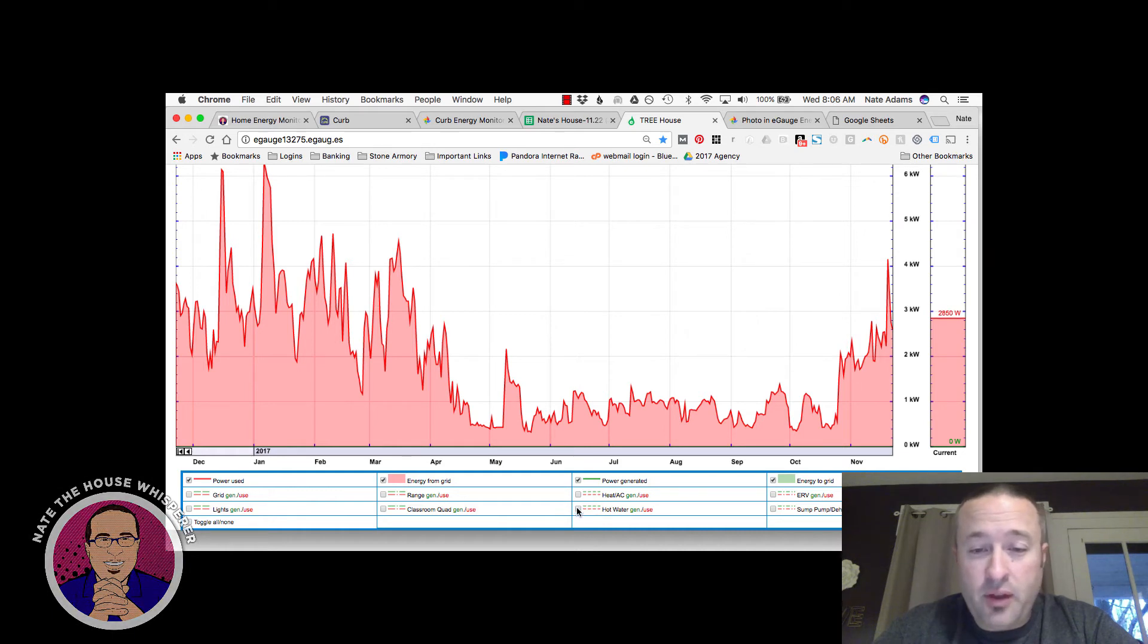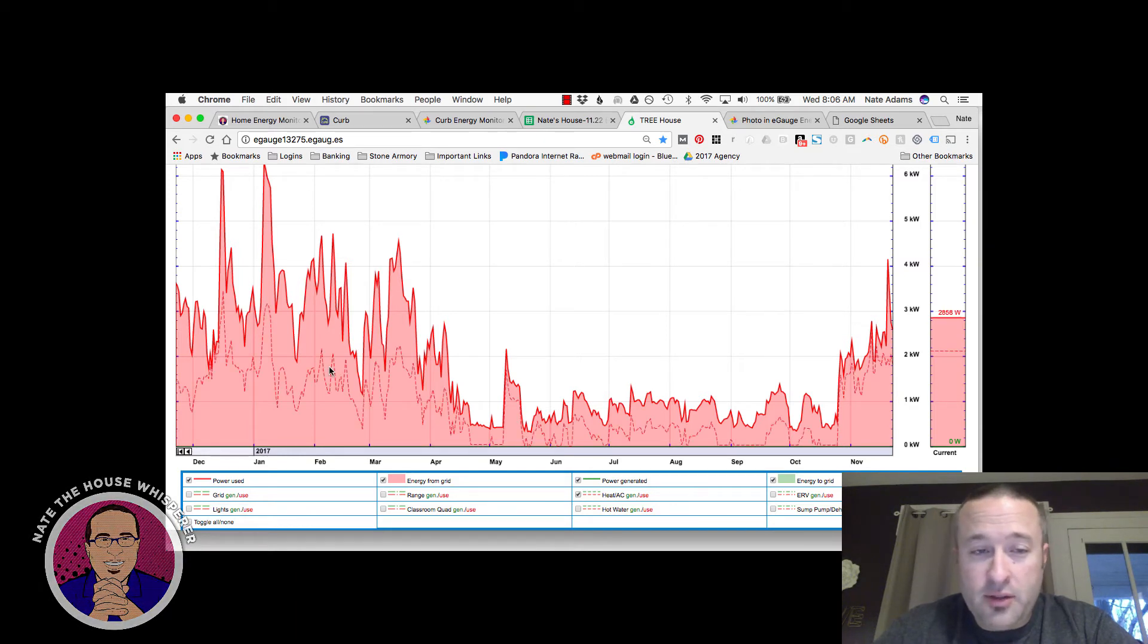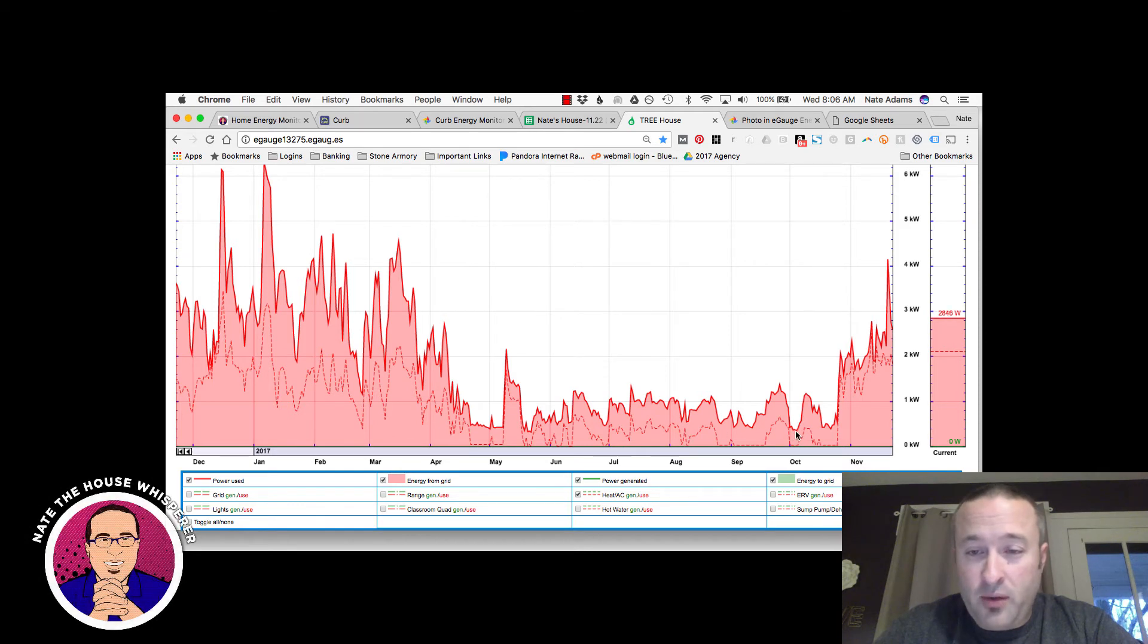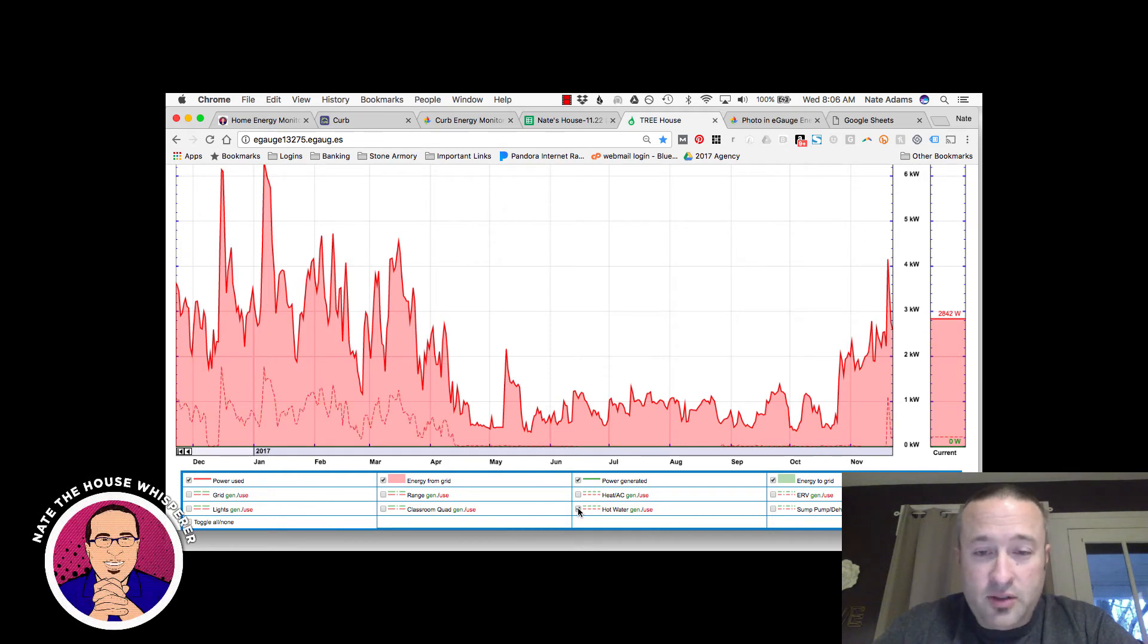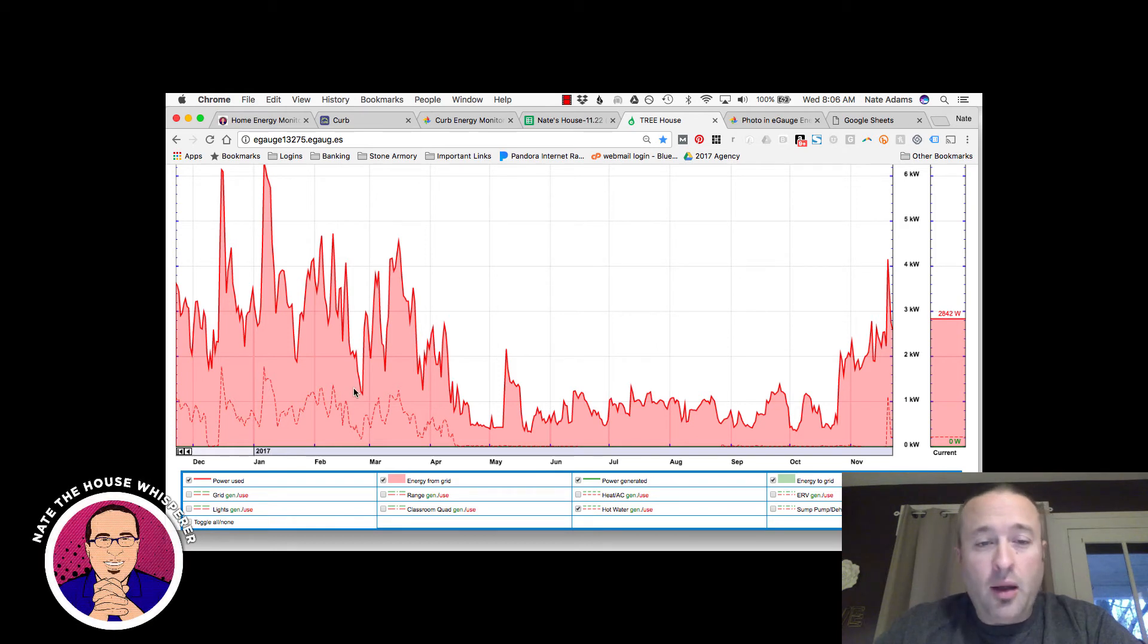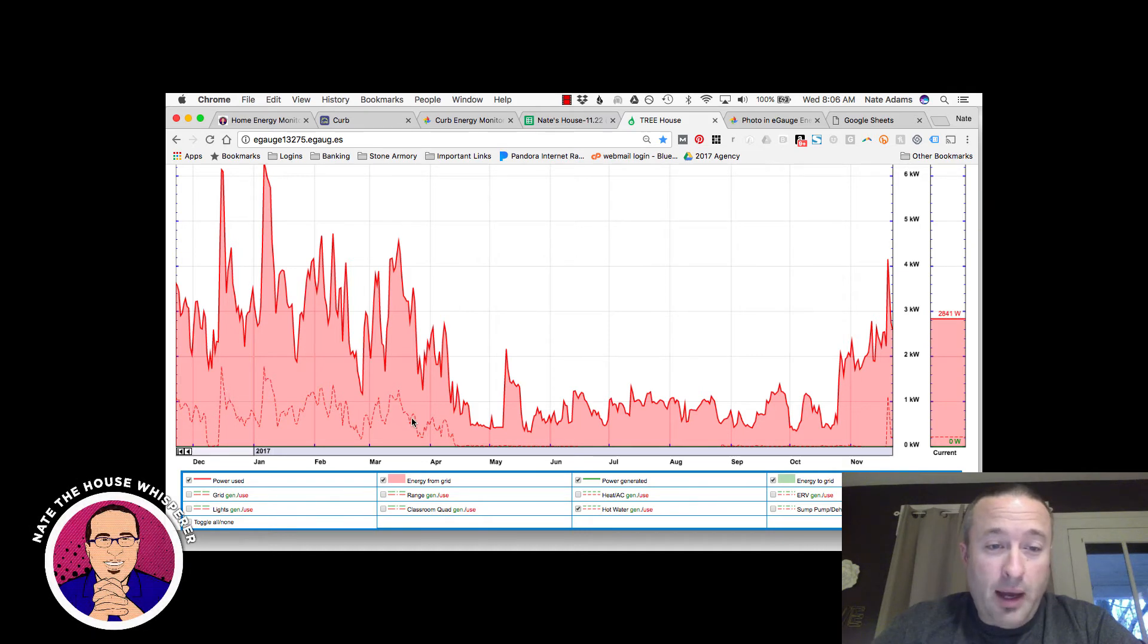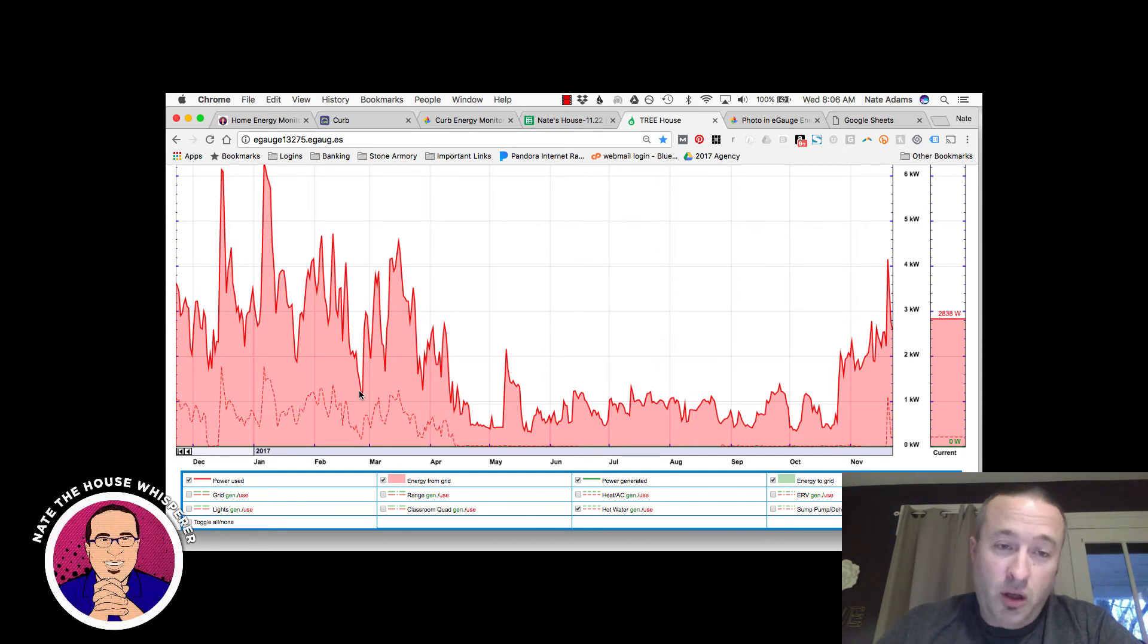So this is looking over the last year. And you can select with E-Gauge which circuit you're monitoring and see what's going on. So the big thing for this that's sucking a lot of juice. Well, there's two different things. One is the circuit with the mini splits. So you can see this dotted red line. That's how much the mini split heat pumps are using throughout the year. And then the other big user is the hot water heater, which this house has a radiant floor in the basement, which probably wasn't the best idea. I would have preferred to just do another mini split down there. But it is what it is. And you can see that it uses quite a bit of power through the winter time because there's no heat in the basement and not a great deal of heat on the first floor of this house.